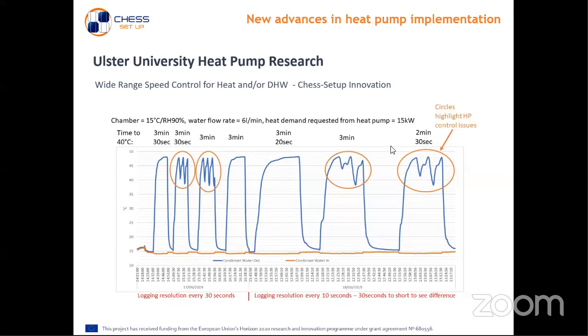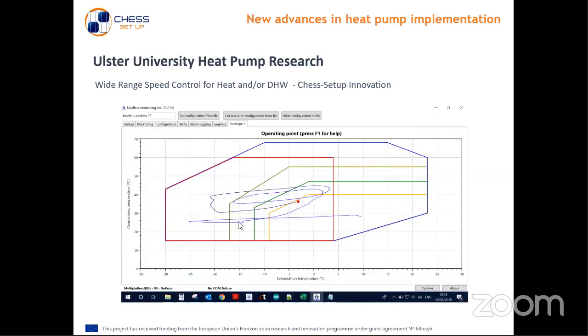So there was these speed changes you can see in some of the graphs. This transmitted itself to when you actually saw what the compressor was doing on its operating point. It was running through ranges of speeds across its operation as it tried to ramp up to deliver a hot water demand fairly quickly or a space heating demand very quickly. So this was referred back to the suppliers, and there's ongoing work on how we make these things more stable.